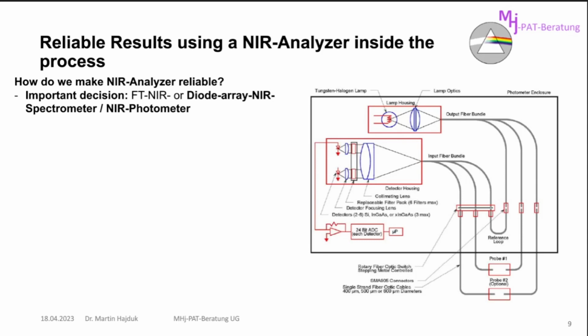Or in this case, I have a picture of my NIR photometer. So in the next slides, I want to have a look at the diode array NIR or the NIR photometer. So we have different parts inside the system. We have a black radiator, that's normally a halogen lamp. Then we have the glass fiber. We have connectors of the glass fibers and go through the sample cell back to the optical system.